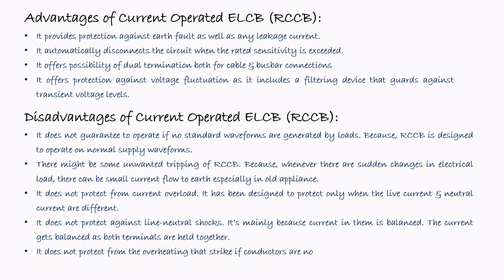It does not protect from the overheating that strikes if the conductors are not properly screwed into the terminals. Then there will be some overheating in the connections in the joint, but the current operated ELCB or the RCCB will not protect this type of condition.